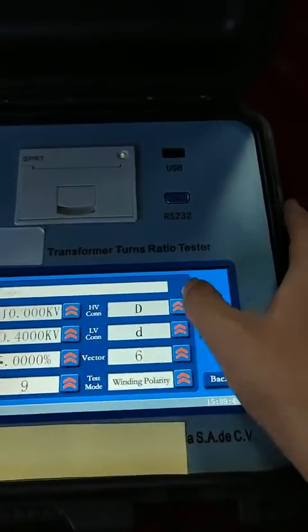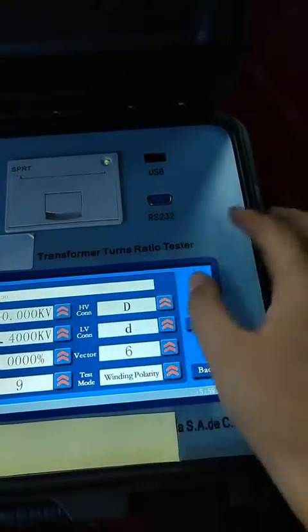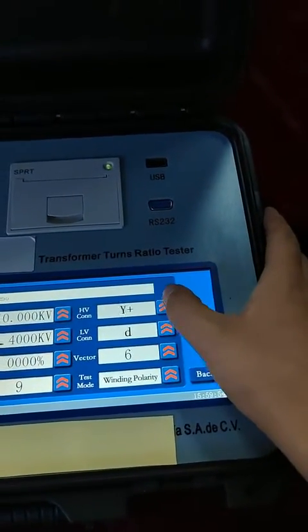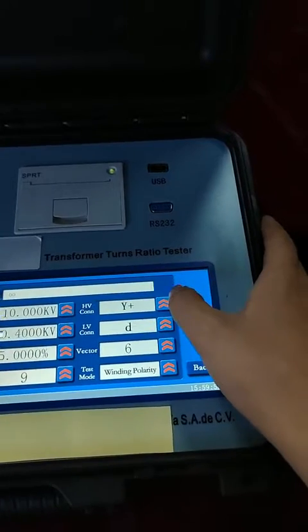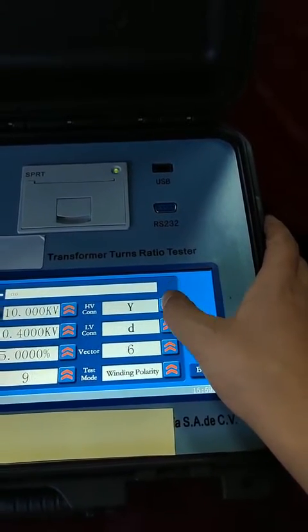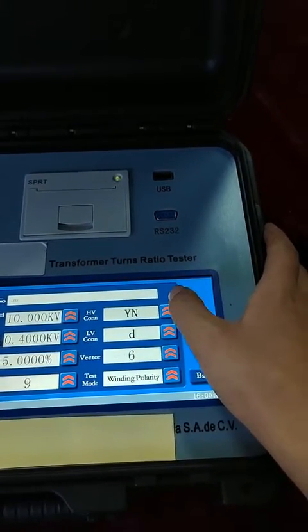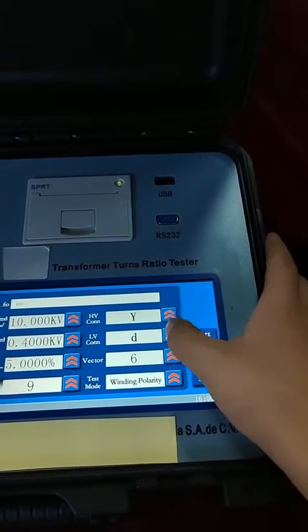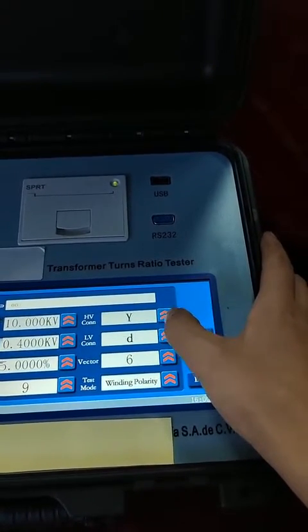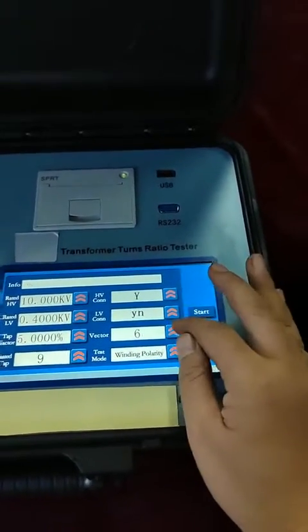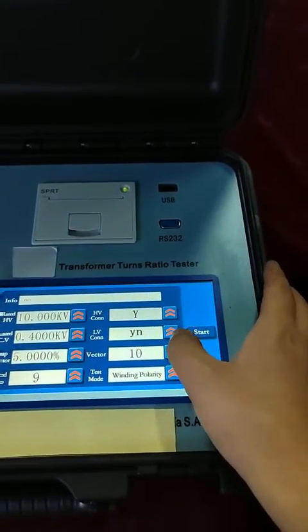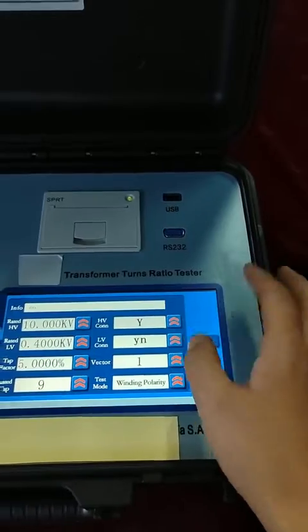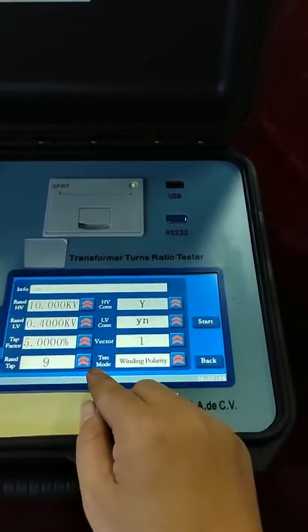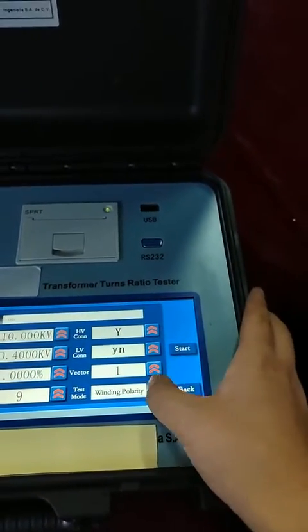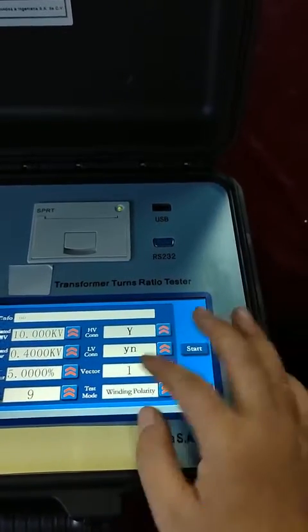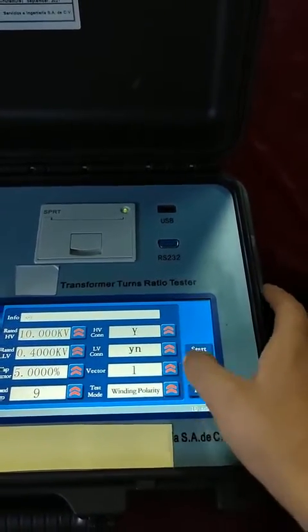You can set up the connection, vector connections here, from high voltage to low voltage, vector from 0 to 11. The test mode lets you choose three-phase or winding polarity test.